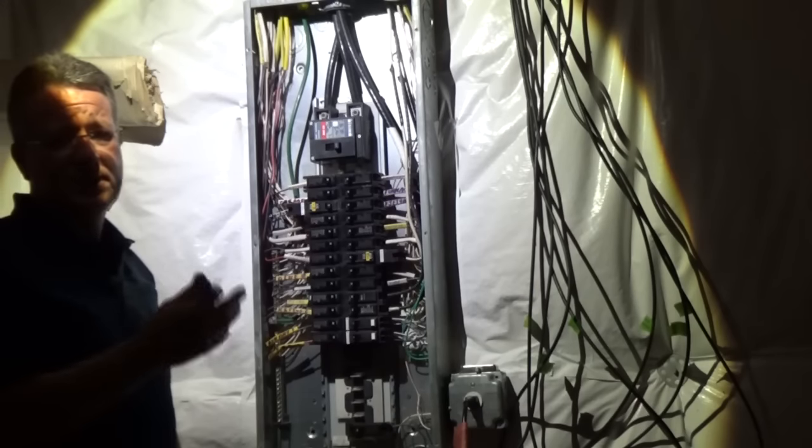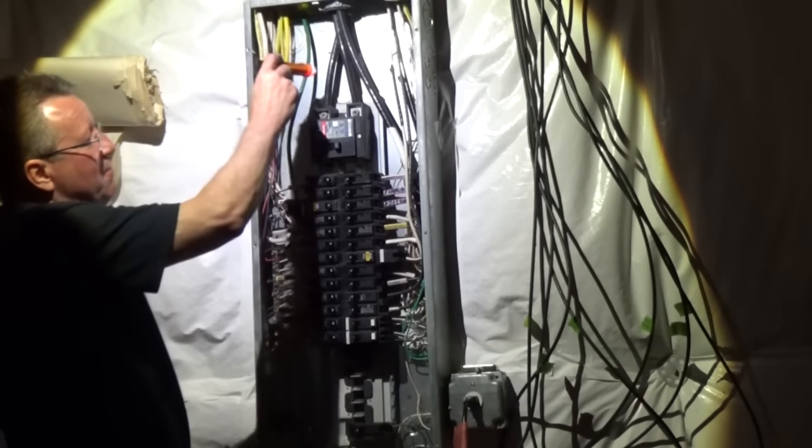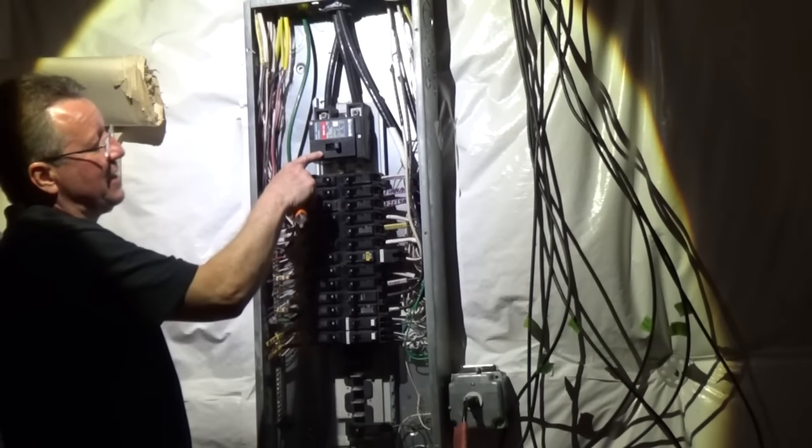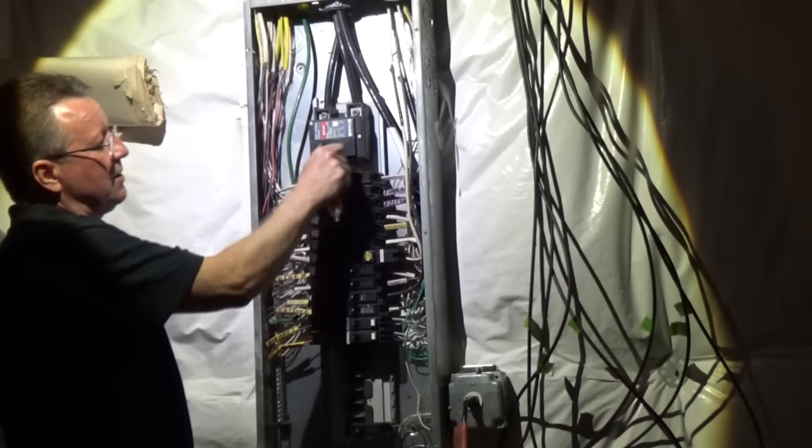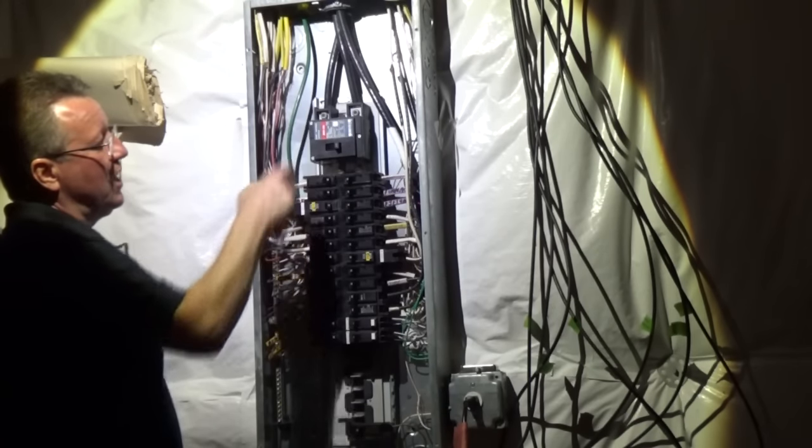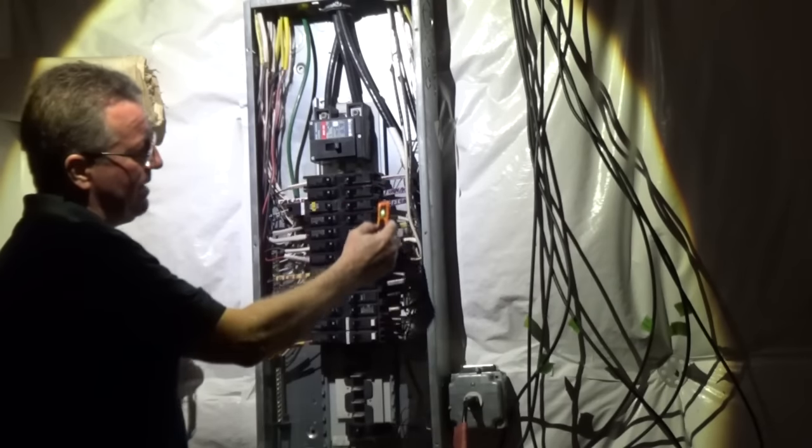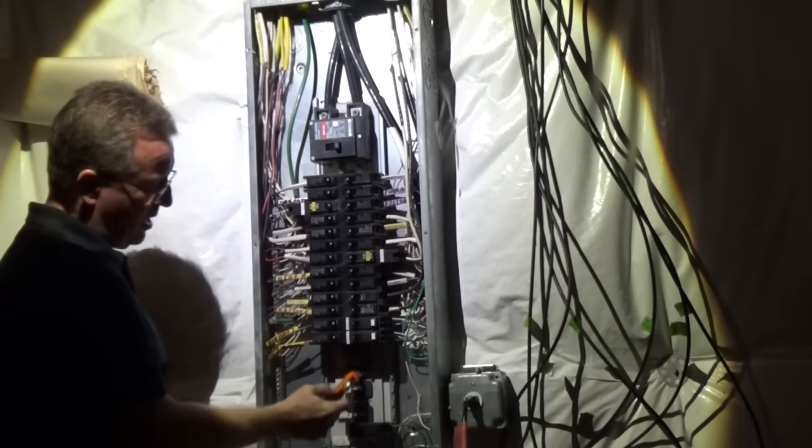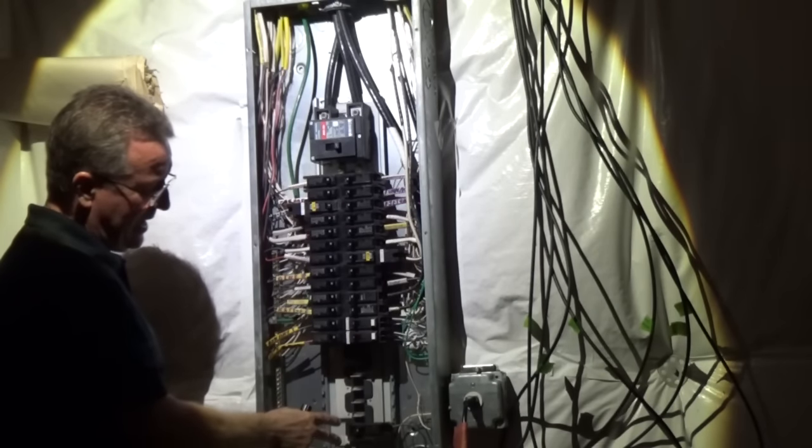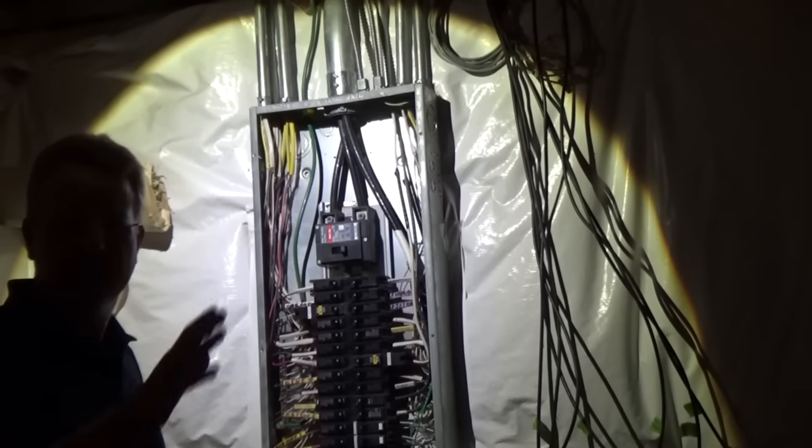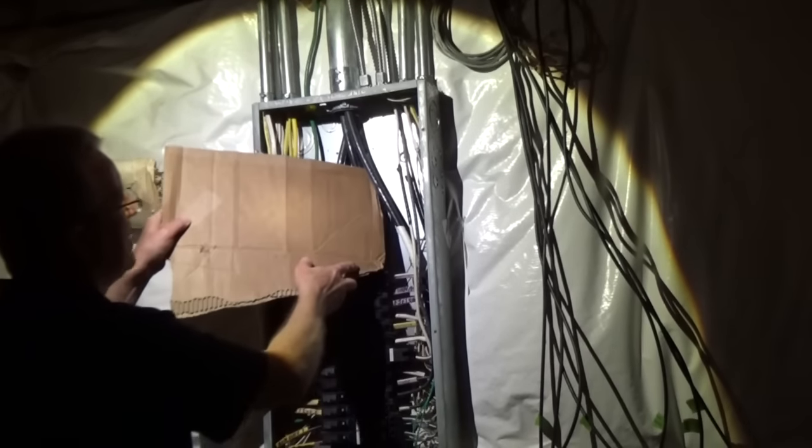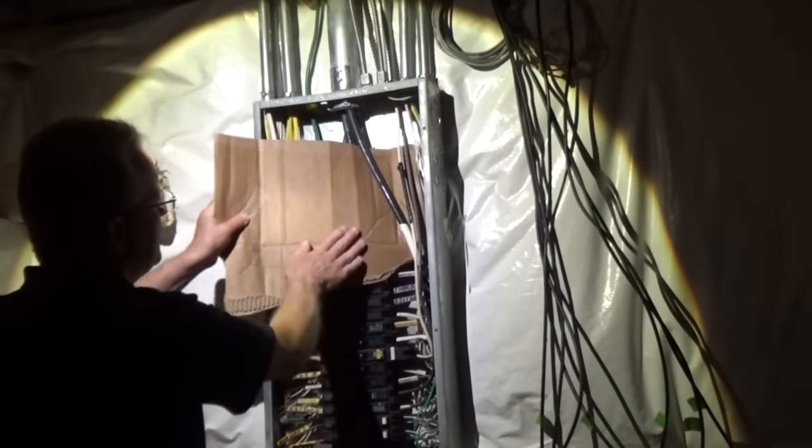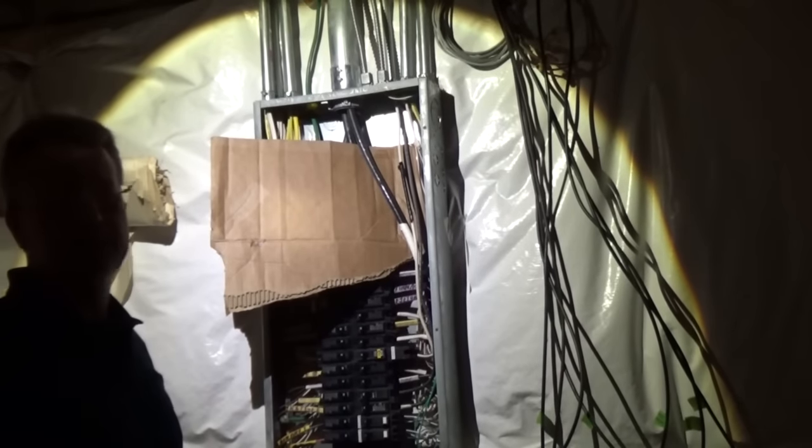Once the cover is removed, stay away from the main wires and also these main lugs by the main breaker. When this is off, those wires are still alive. Everything here is off, and this is where we're going to be adding our new breaker. For safety, you can cover the main lugs with a piece of cardboard. That way you just don't accidentally bump into it.